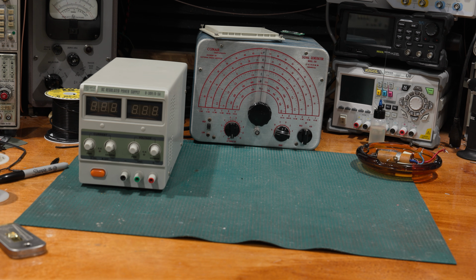The purpose of that video was not to see how close I was to the current definition of the volt. It was to see which calibration units agreed with each other and which needed to be adjusted to agree with each other. And then taking the three that agreed with each other, pseudo-averaging them. I did not average them. But looking at their deltas on the 7510 to the limits of its accuracy, picking the best one and moving forward from there. This let me set a base plane of DC accuracy here for the lab, at least as the best we could measure it for right now. This is always improving, and you guys are along for the ride, so as it gets better here, you'll figure out how we're doing that and what we're doing to do that.